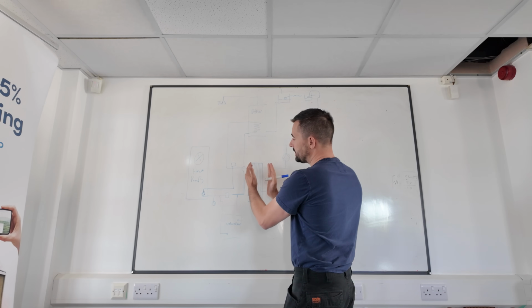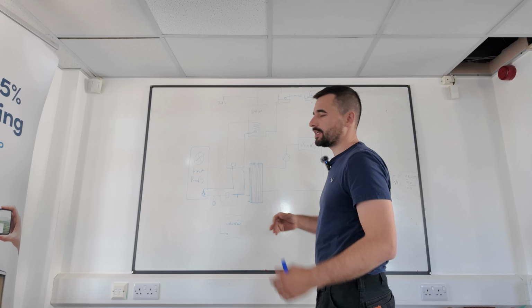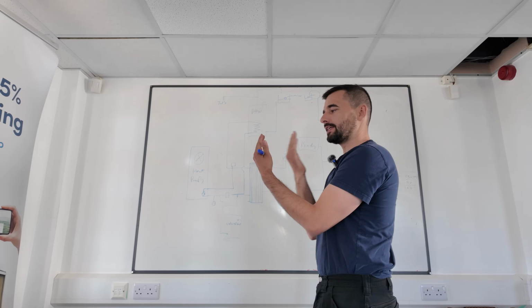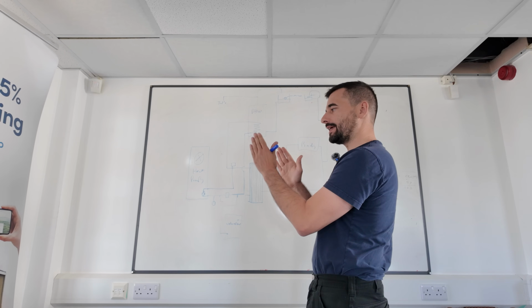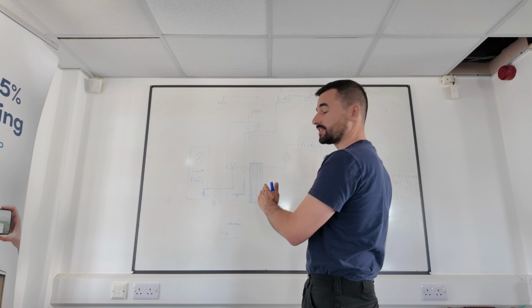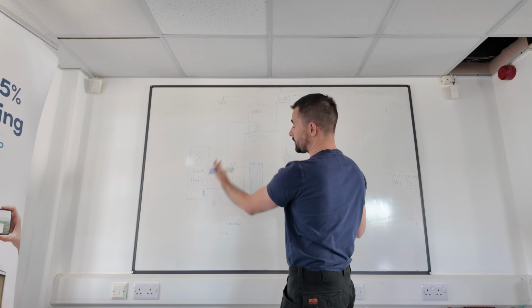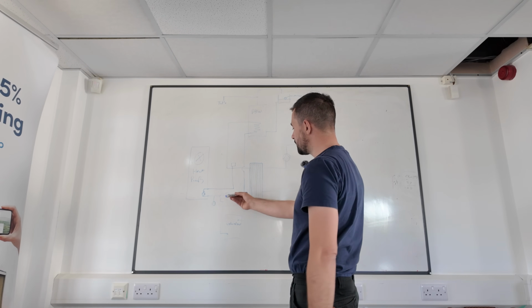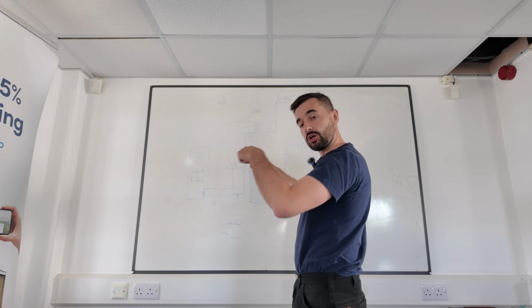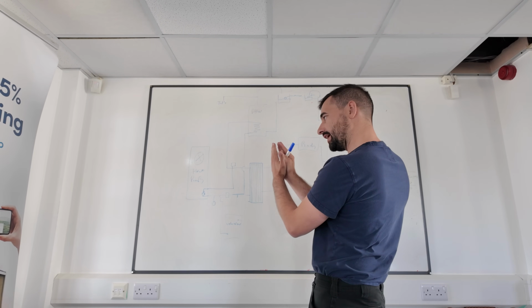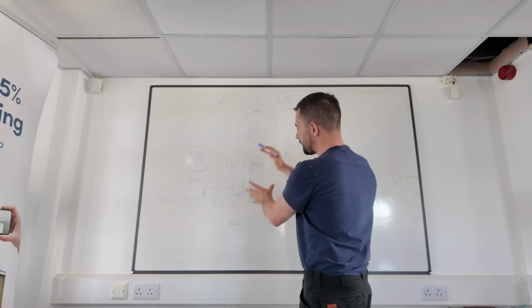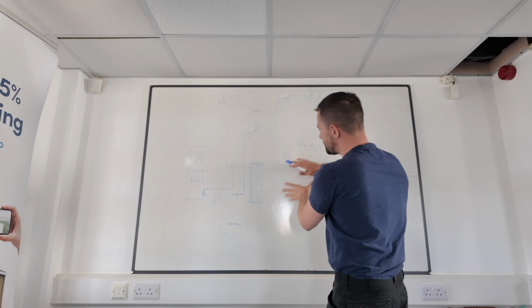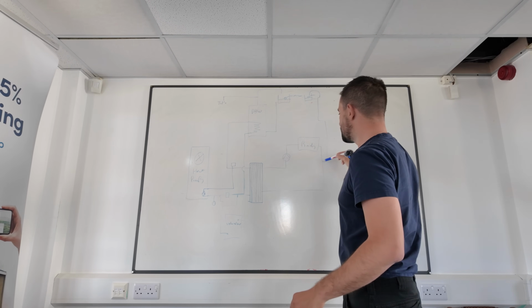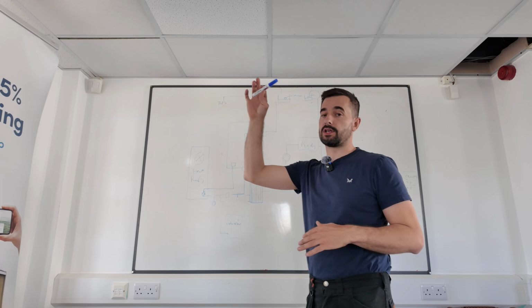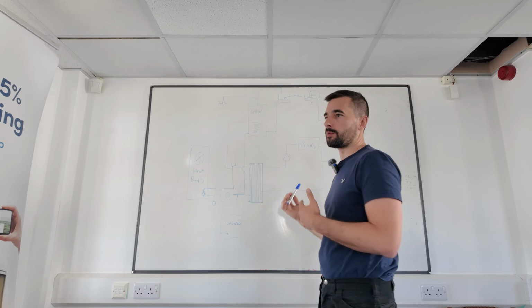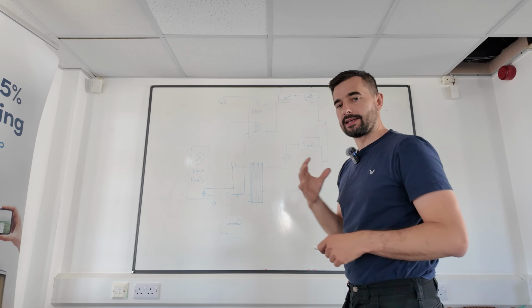So this heat exchanger has been installed, and it's a plate-to-plate heat exchanger. It's a gasketed heat exchanger, so we put layers of plates with gaskets in between, and every alternate plate will have one side of the system water in, and the other alternate plate will have the pressurized side of the system in. So ultimately, you imagine the water's going up one side, skipping a plate and coming down the next one. So we can exchange the heat from plate to plate. So that goes in, all that side's pressurized. This side then can be left with the header tank in the loft to keep it pressurized just on the head of water from the tank in the loft. So it'll be much lower pressure, less than half a bar with the height of that building.